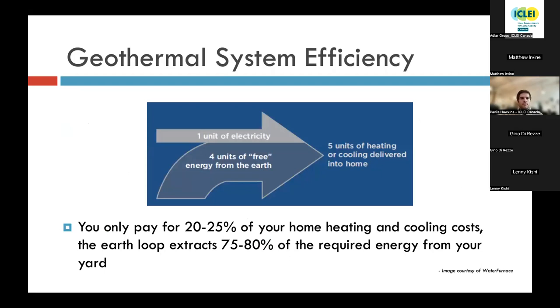Visually, what this looks like is one unit of electricity purchased allows the system to extract up to 4 units of free energy from the earth. That ends up being 4 to 5 units of heating or cooling delivered into the home. And this is how geothermal systems save so much money compared to conventional, is that you are only paying for 20 to 25% of your home heating and cooling costs. The earth loop is actually extracting 75 to 80% of the required energy from your yard. That 75 to 80% is that large amount of low-grade heat that we are compressing into a usable amount of high-grade heat. Next slide, please.